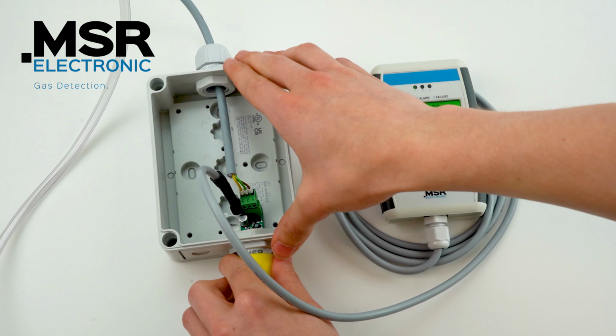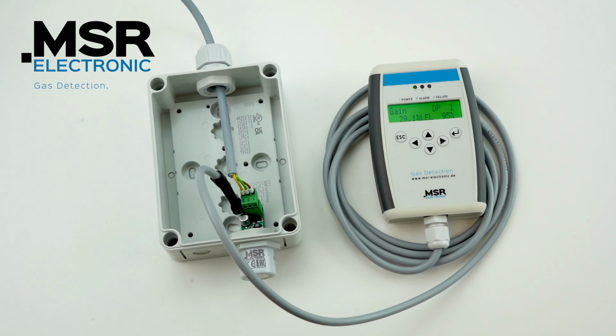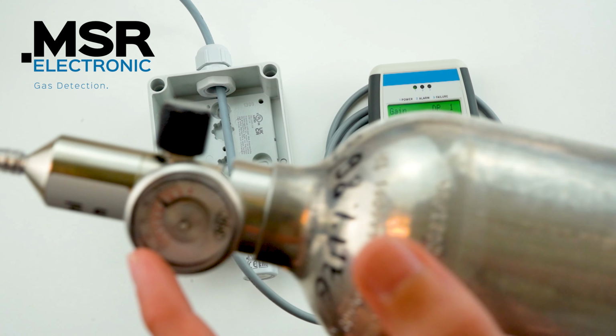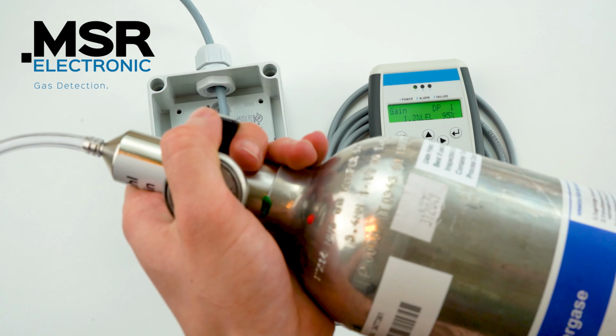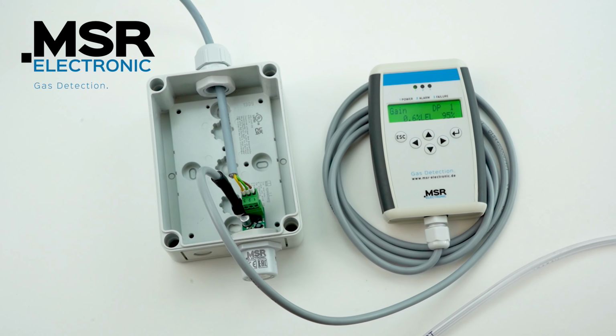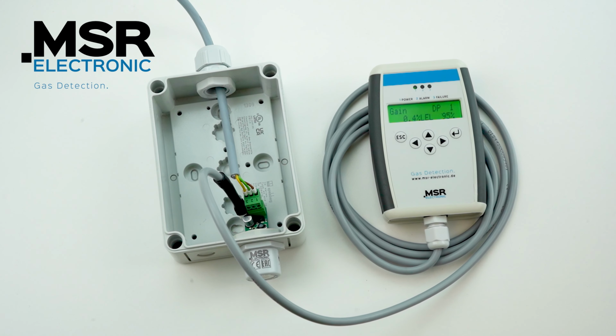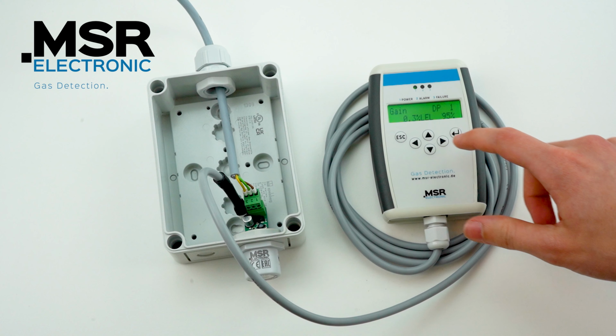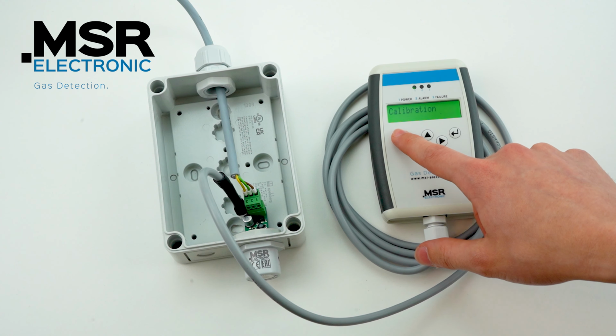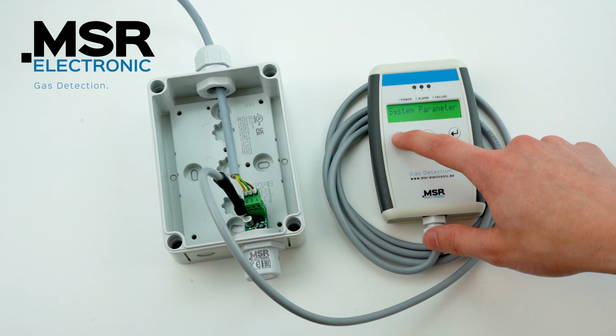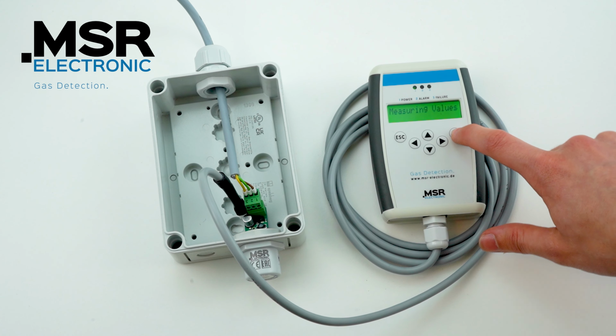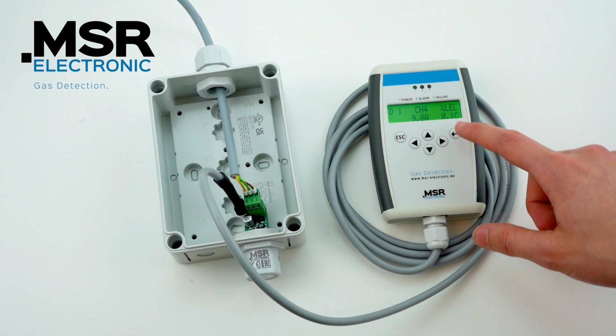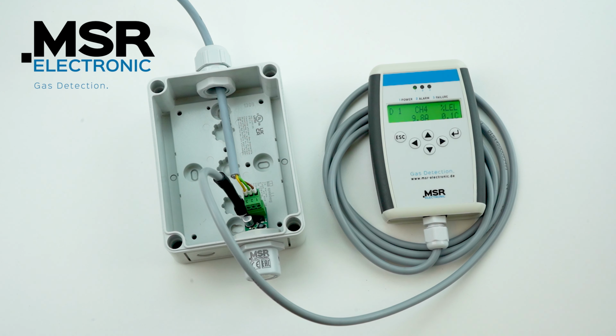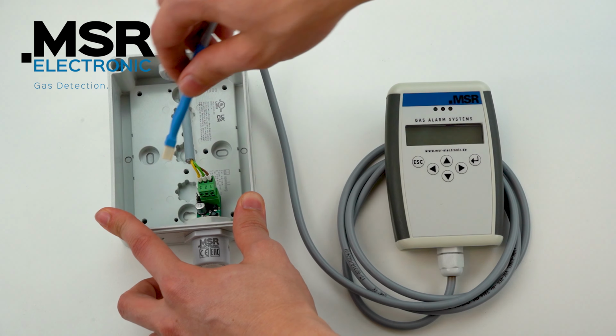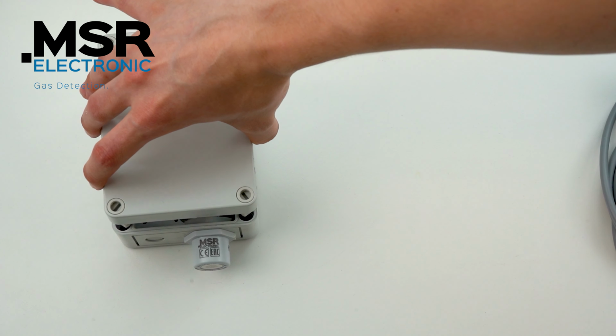After successful calibration, the sensor cap can be removed and the flow regulator can be unscrewed from the gas cylinder and the sensor reading can be checked again. Finally, the device is restored to its original state by closing the lid and tightening the screws.